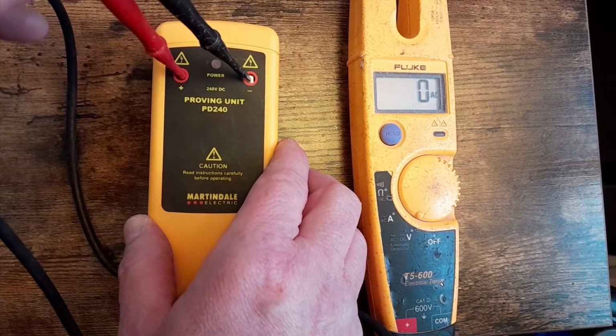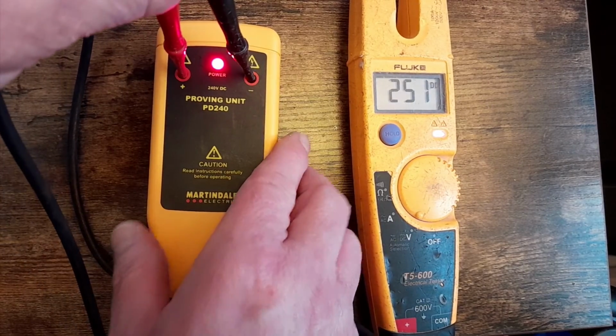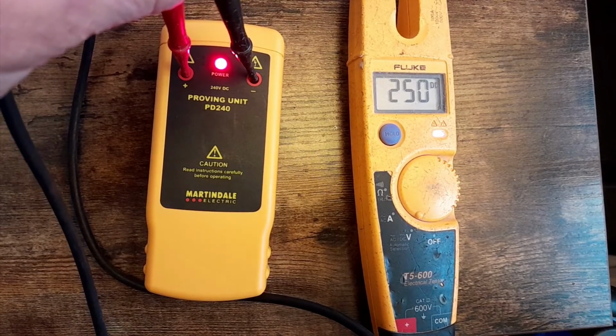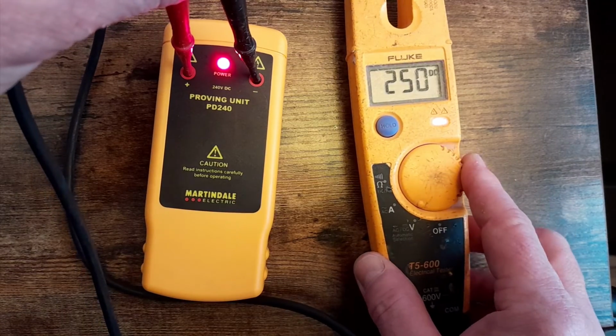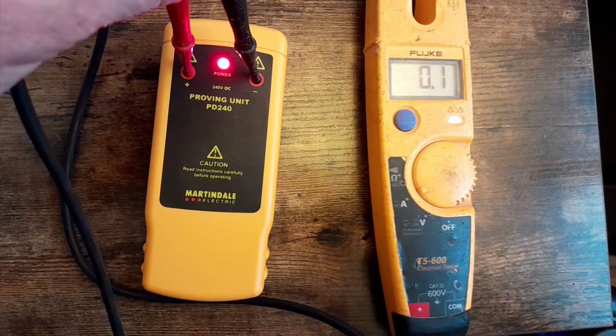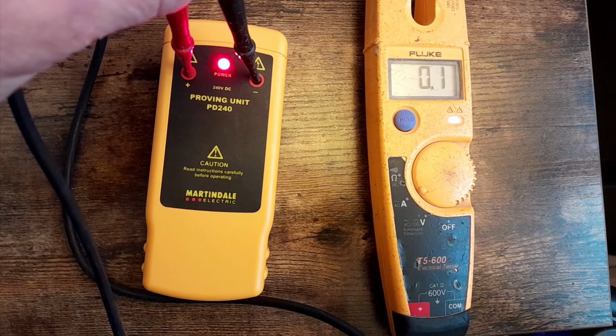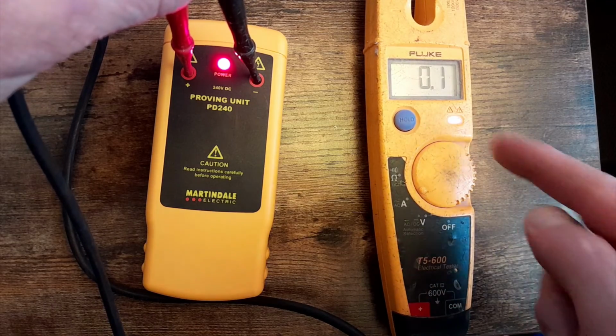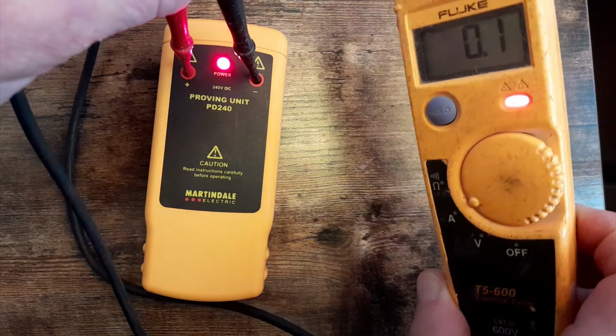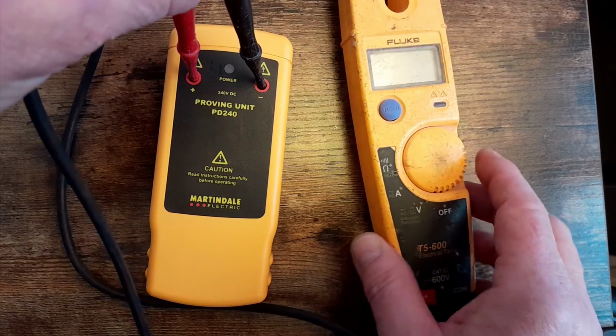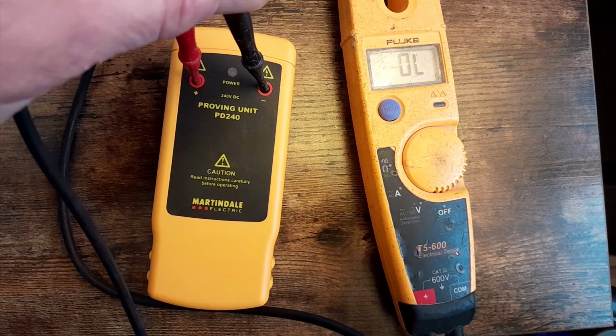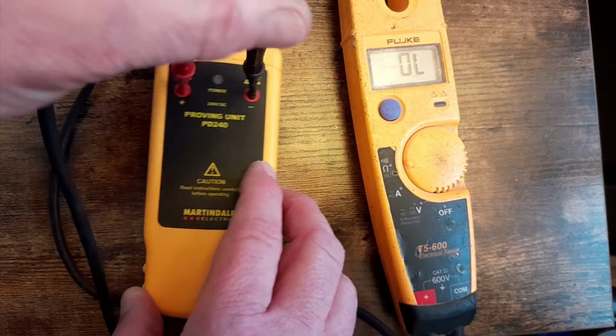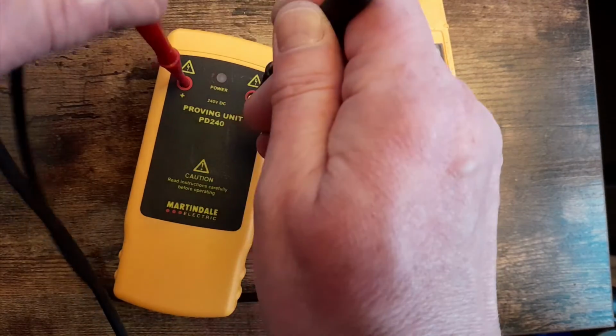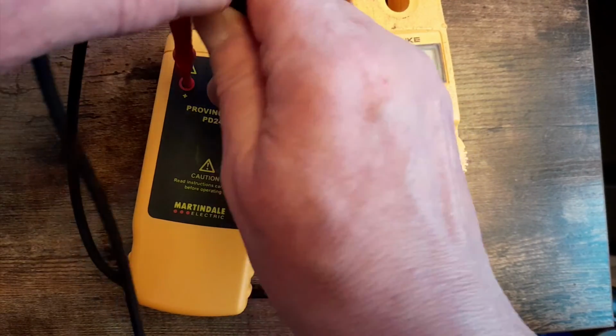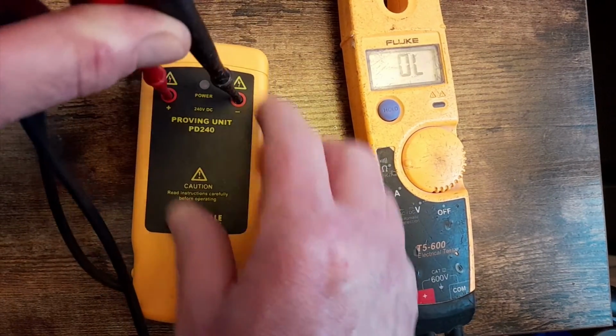And here we can see on this voltage indicator that having the wrong setting can give you misleading readings. I switch it to current and get 0.1. The little indicator light comes up there to say there's some kind of voltage present. But if you're unsure of your tester, that could cause you some confusion. And if you put it onto continuity, the proving unit doesn't seem to want to work and you just get OL. And you might get misleading readings, especially when you're inexperienced.